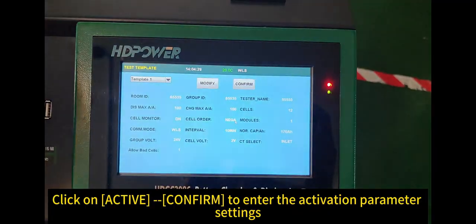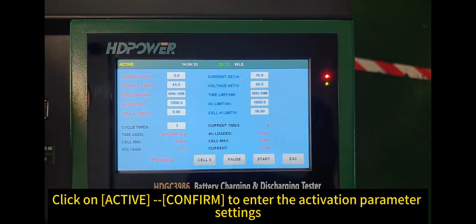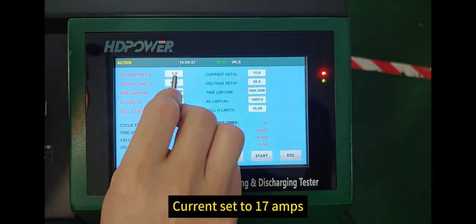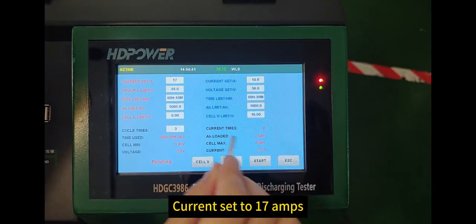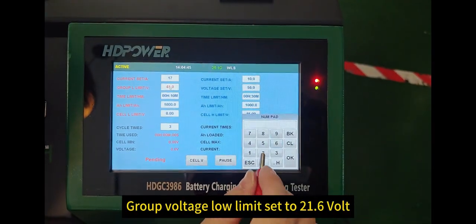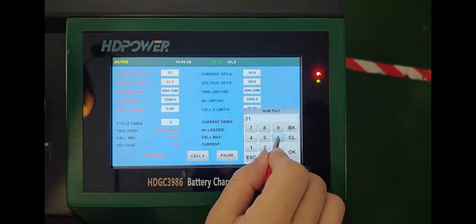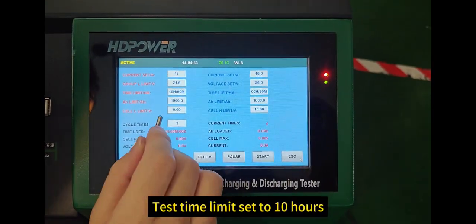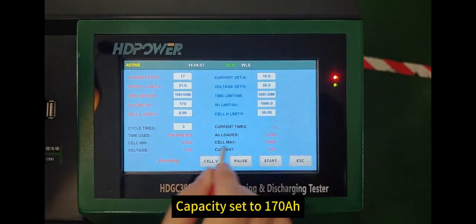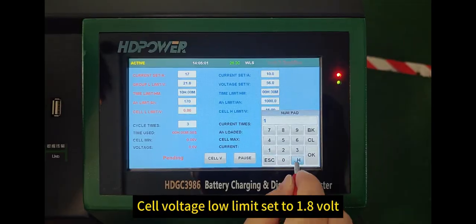Click on Active, confirm to enter the activation parameter settings. Current set to 17 amps. Group voltage low limit set to 21.6 volt. Test time limit set to 10 hours. Capacity set to 170 Ah. Cell voltage low limit set to 1.8 volt.